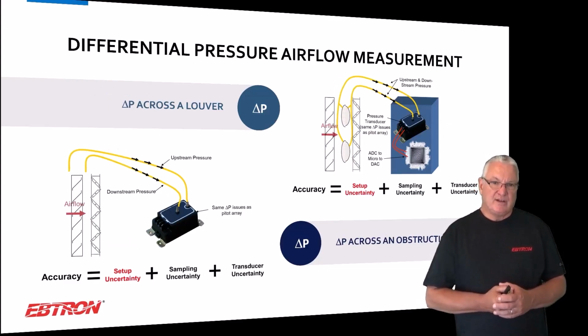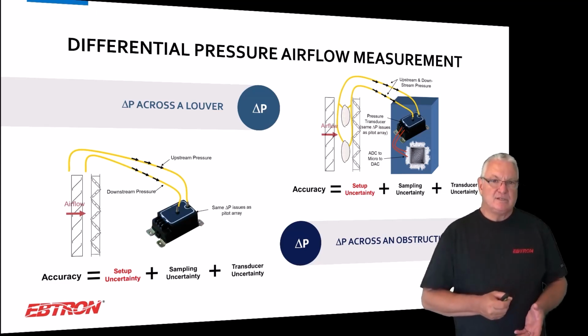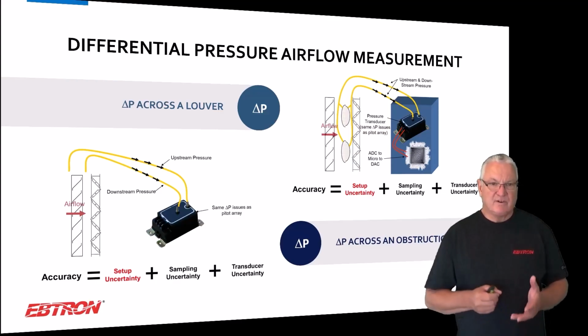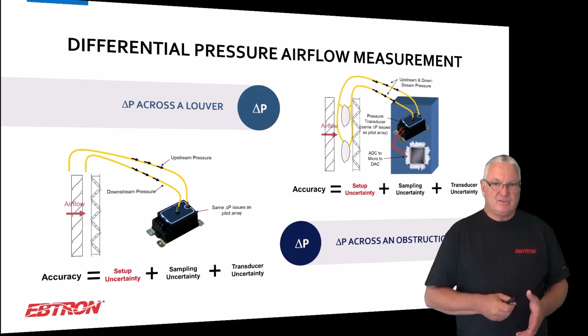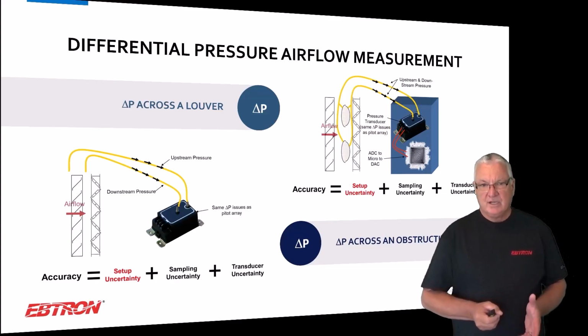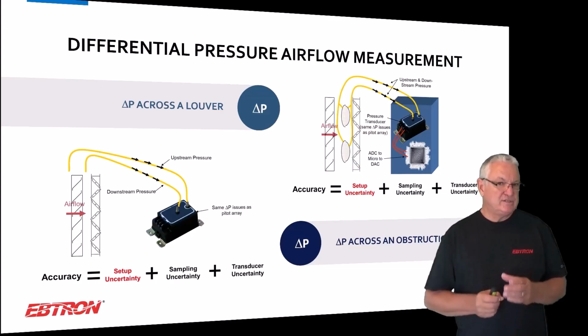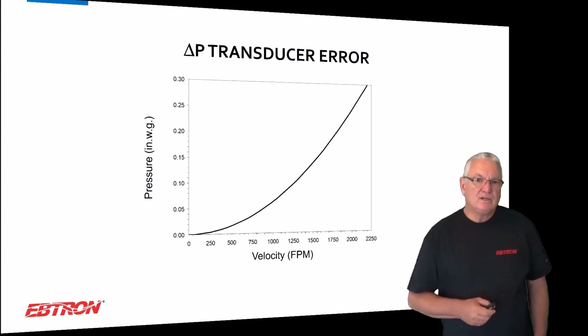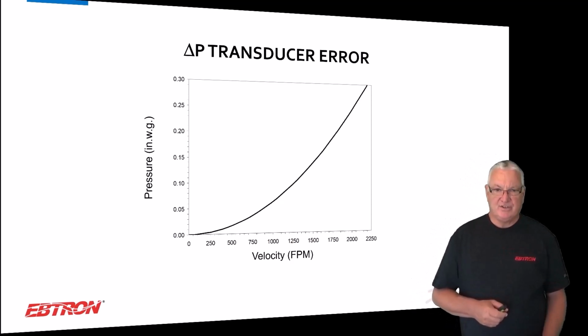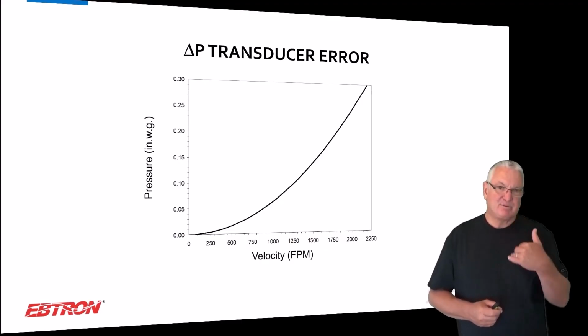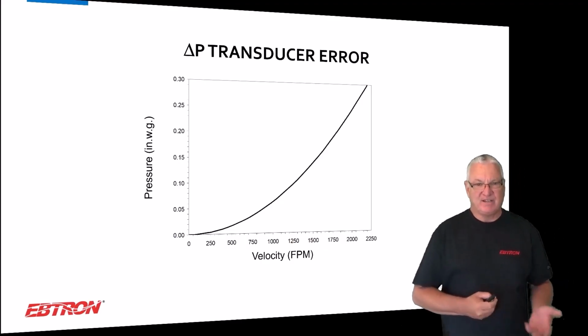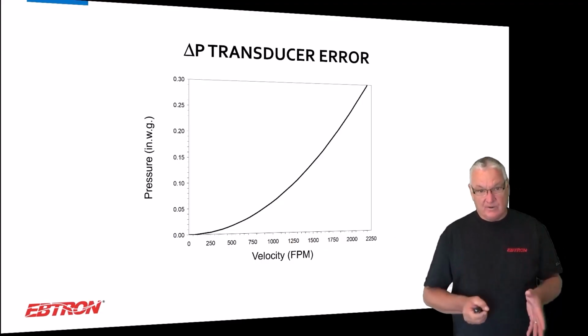Other differential pressure devices have similar issues, like measuring a DP across a louver. A louver is relatively low pressure. You don't know the flow coefficient. You've got to set it up, but the relationship to flow is the same. And then there are even other devices out there that measure, I call it, the pressure drop across obstructions. Again, a very similar situation, but all of these just use a single pressure sensor. And so one of the things we have to look at is pressure sensors. So you have a relationship. This is a square root relationship. I know some of you say, oh, that's a square relationship. Well, the way I have the axes, I have pressure on one axis and velocity on the other, but it's really a square root relationship to flow.